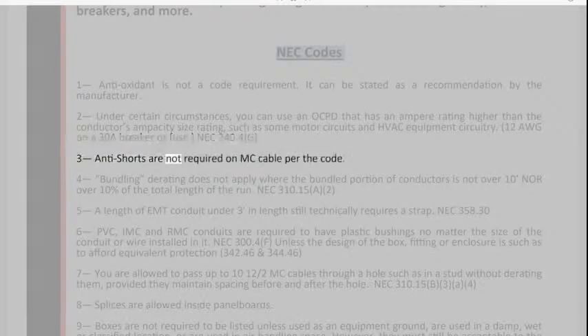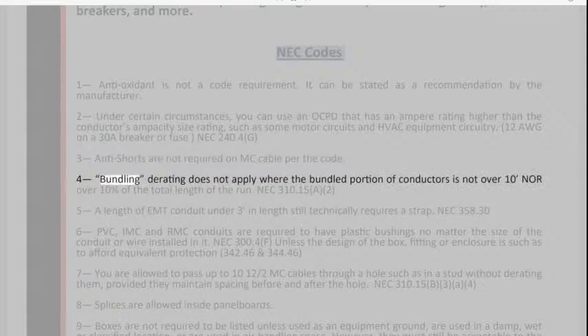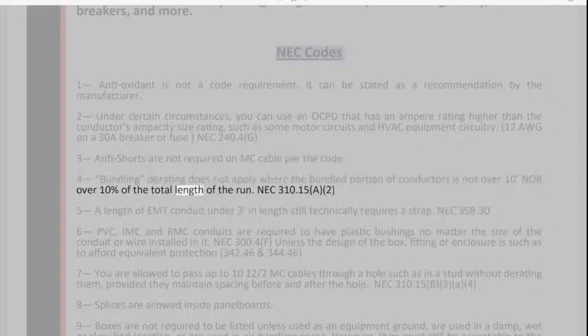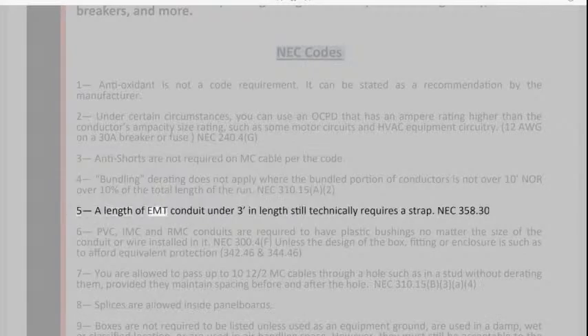3. Anti-shorts are not required on MC cable per the code. 4. For bundling, derating does not apply where the bundled portion of conductors is not over 24 inches nor over 10% of the total length of the run. NEC 310.15A2. 5. A length of EMT conduit under 3 feet in length still technically requires a strap.